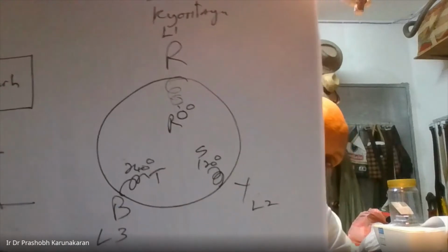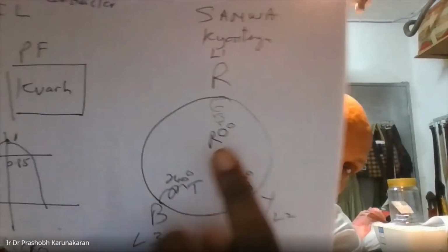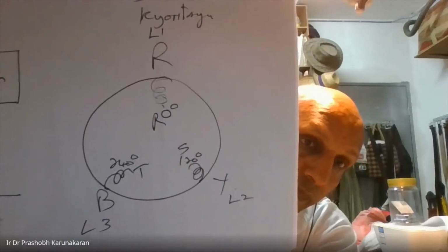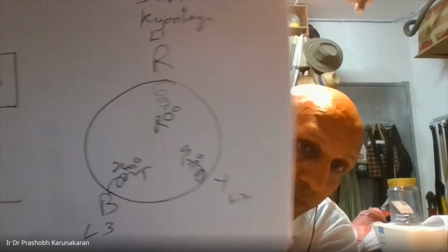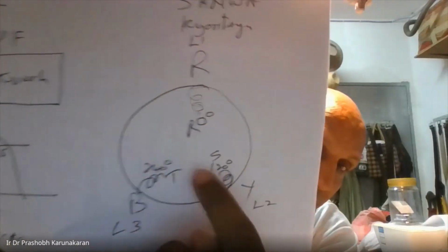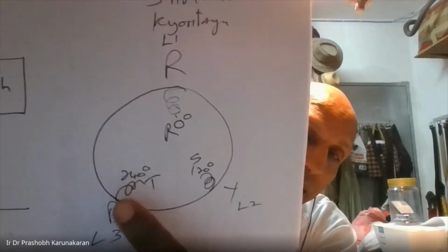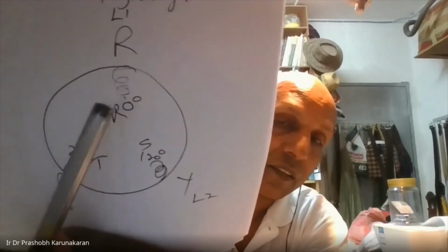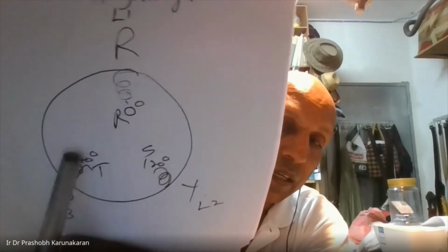Why you need to know this is just because it's on all MSB in Sarawak, for red, yellow, blue, because we normally put this as red, yellow, blue, right? Inside the generator, the three coils are red, yellow, blue, which the Americans call L1, L2, and L3. Red, yellow, blue is British. The American L1, L2, L3 is followed by a lot of countries. And then in Sarawak MSB, I don't know for what reason, they tend to use RST. Maybe it's an old British standard, I don't know. So R is 0 degrees, 120 degrees, and 240 degrees.